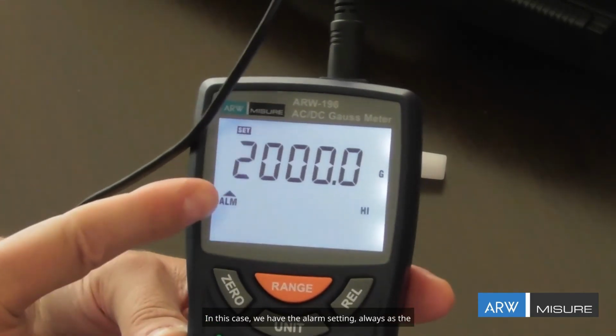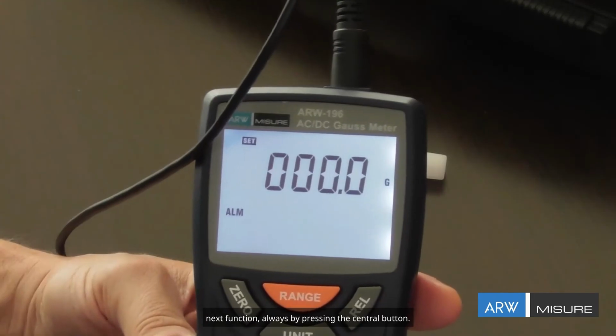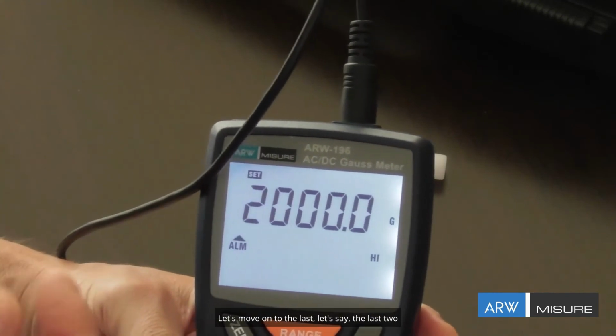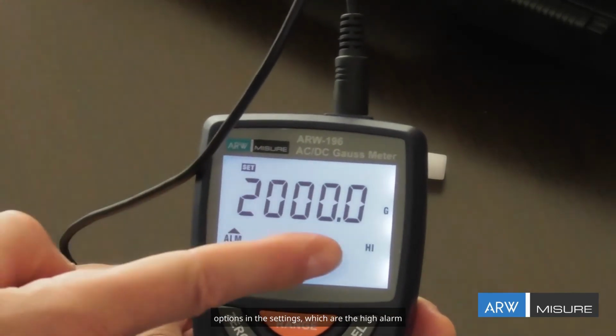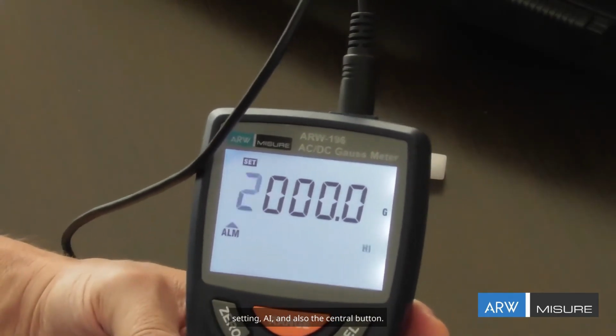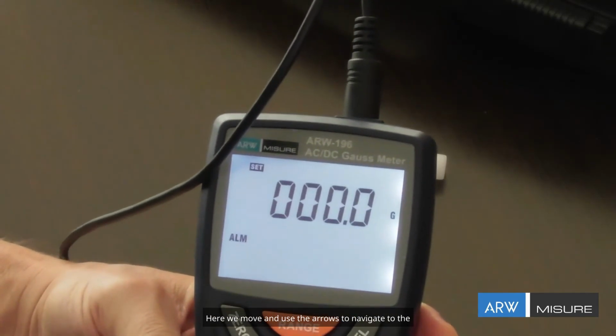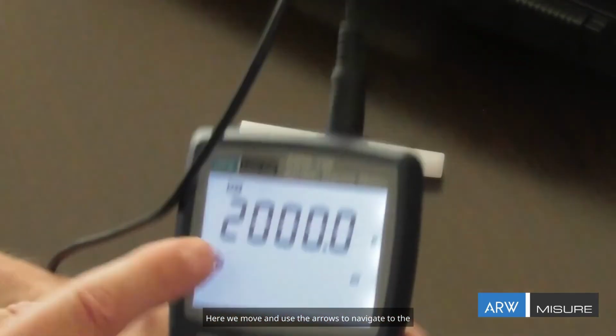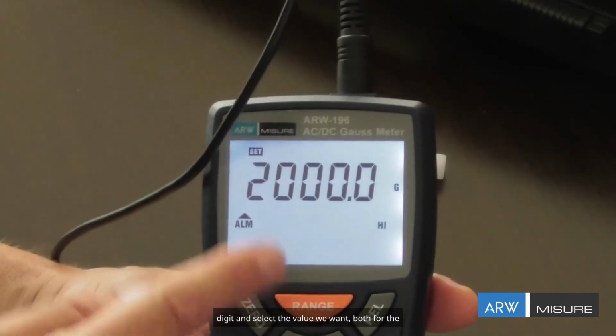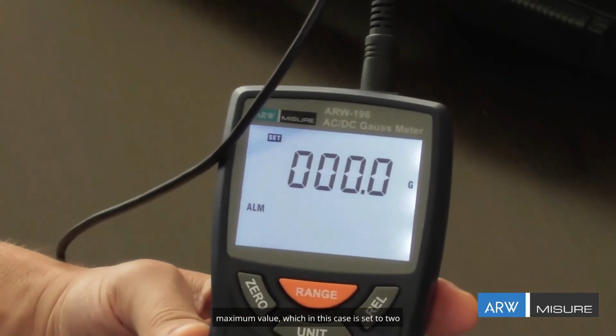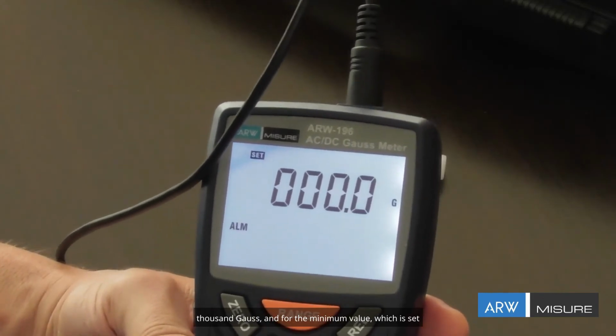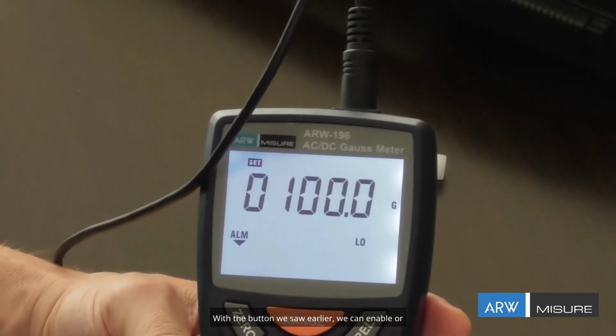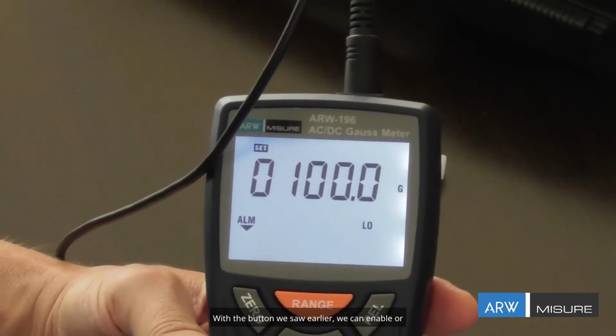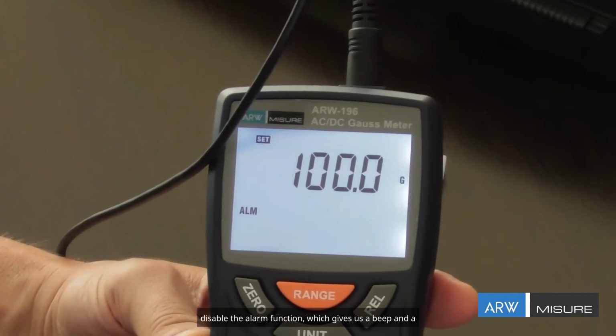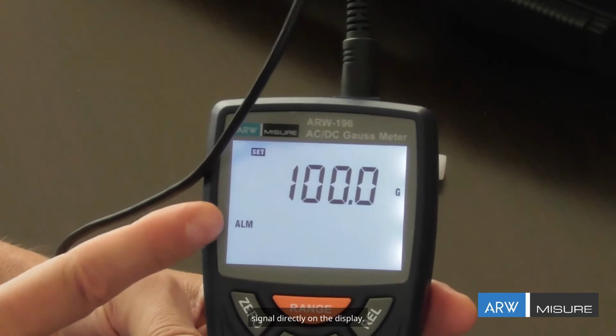In this case, we have the alarm setting as the next function, always by pressing the central button. Let's move on to the last two options in the settings, which are the high alarm setting and the low alarm setting, also with the central button. Here we use the arrows to navigate to the digit and select the value we want, both for the maximum value, which in this case is set to 2000 Gauss, and for the minimum value, which is set to 100 Gauss. With the button we saw earlier, we can enable or disable the alarm function, which gives us a beep and a signal directly on the display.